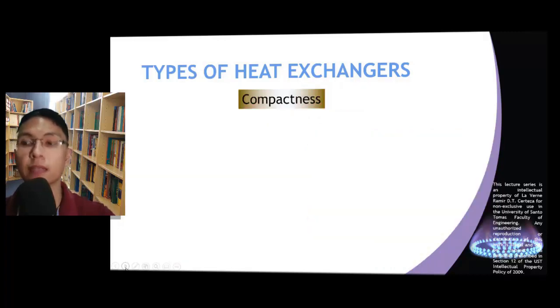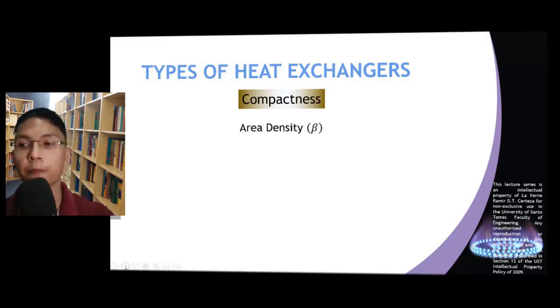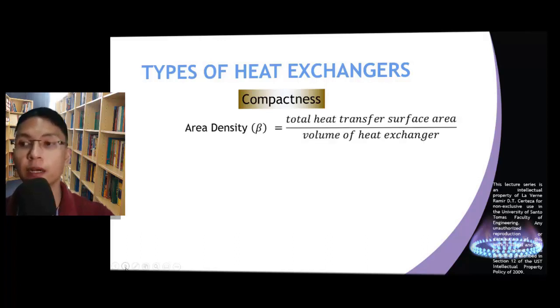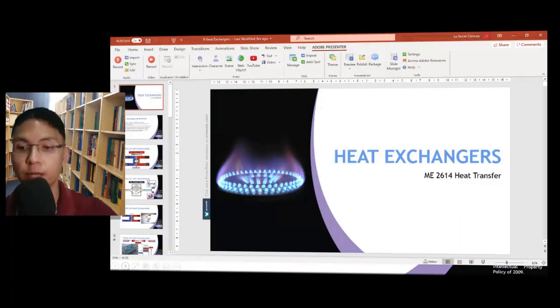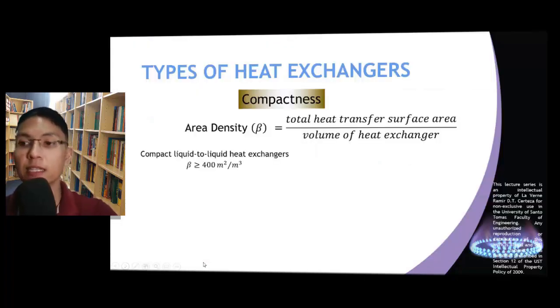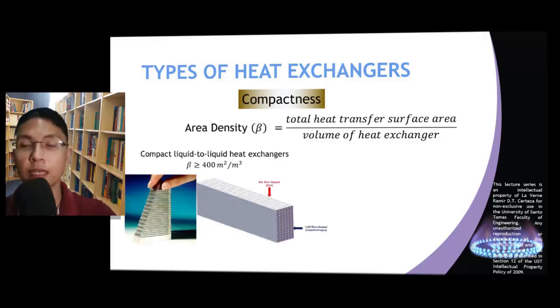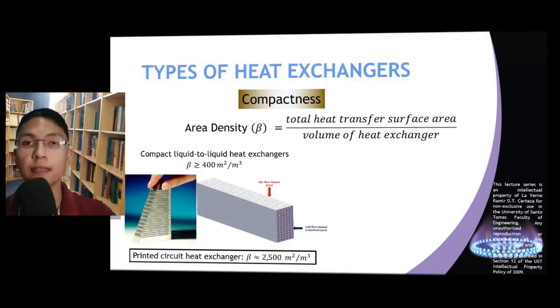The next characteristic by which we can categorize heat exchangers is related to their degree of compactness. We can determine how compact a heat exchanger is using the parameter called area density, often denoted by the Greek letter beta. It is computed by dividing the total surface area where heat transfer occurs by the total volume of the heat exchanger. For heat exchangers in which the heat transfer fluids are liquids, it can be considered compact if its area density exceeds 400 square meters per cubic meter. An example is the printed circuit heat exchanger, which has an area density of approximately 2500.